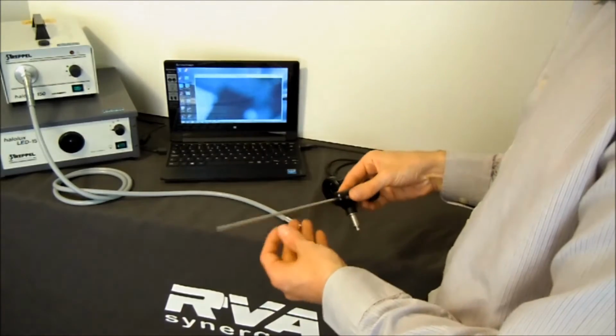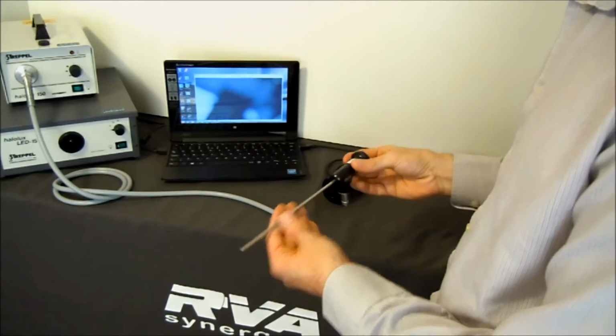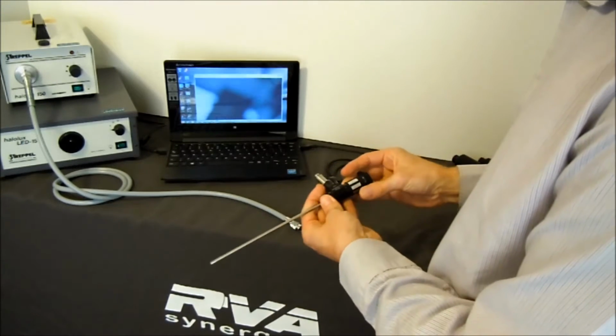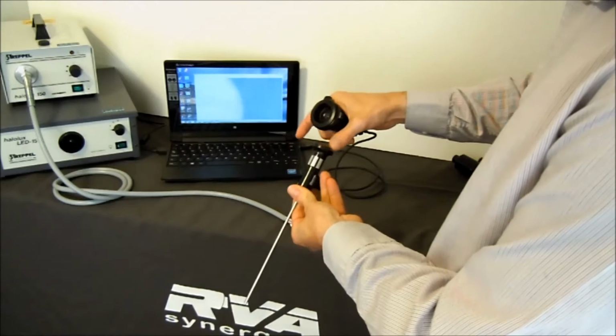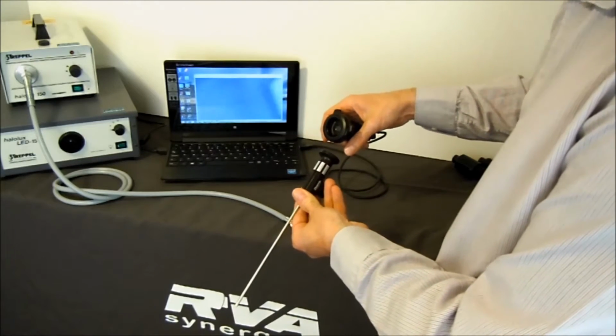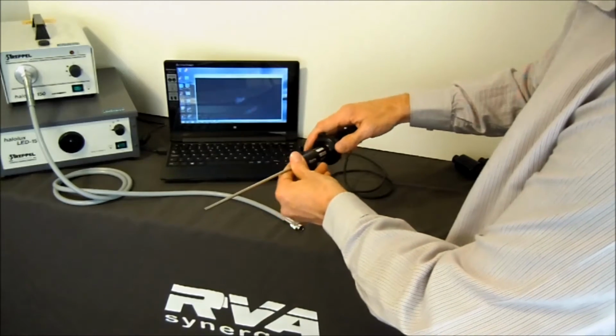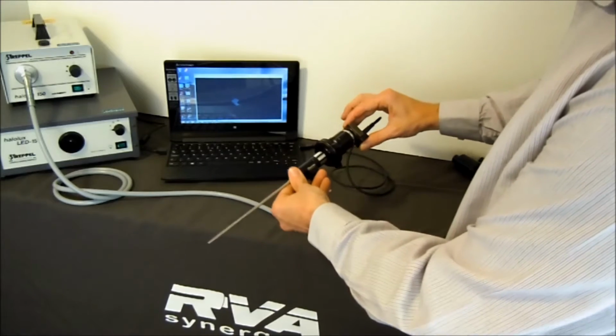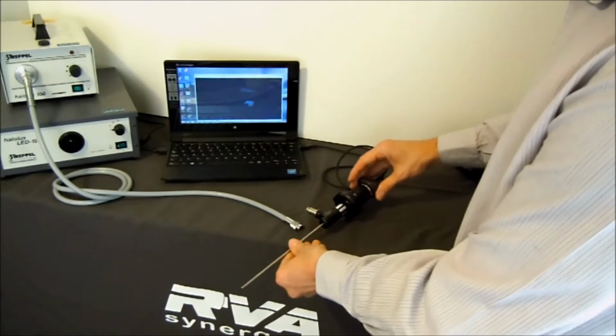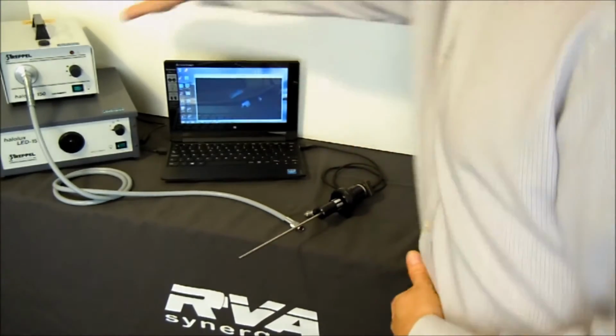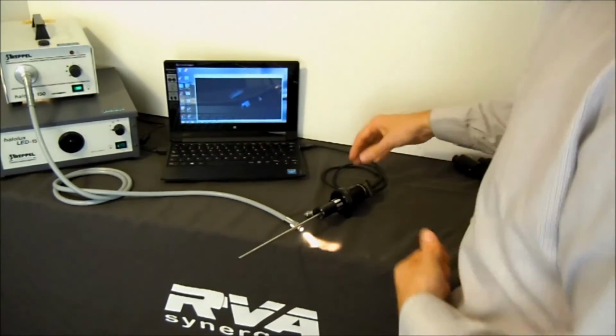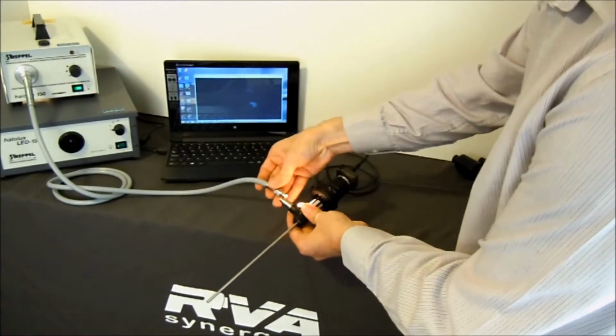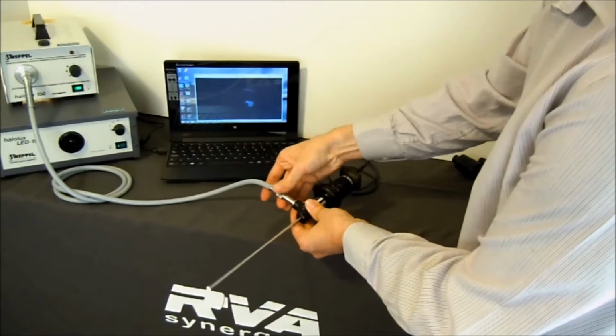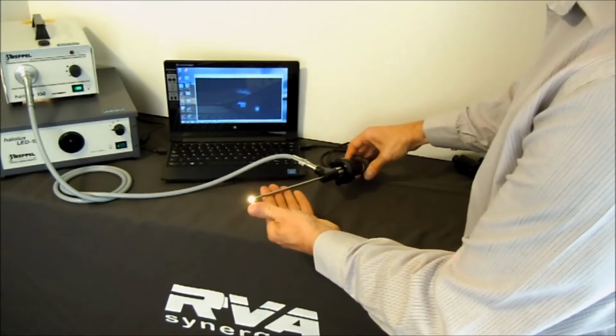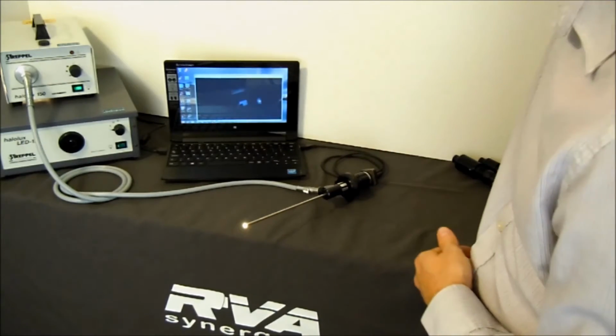First we're going to try a traditional 4mm rigid endoscope with focusing. As you can see, it has an industry standard 31.75mm eyepiece, which just clips into the camera receptacle like that. Next we're going to connect the light source. So we're going to switch on our halogen light source here. Connect it to the endoscope like that. And now we have our system connected.